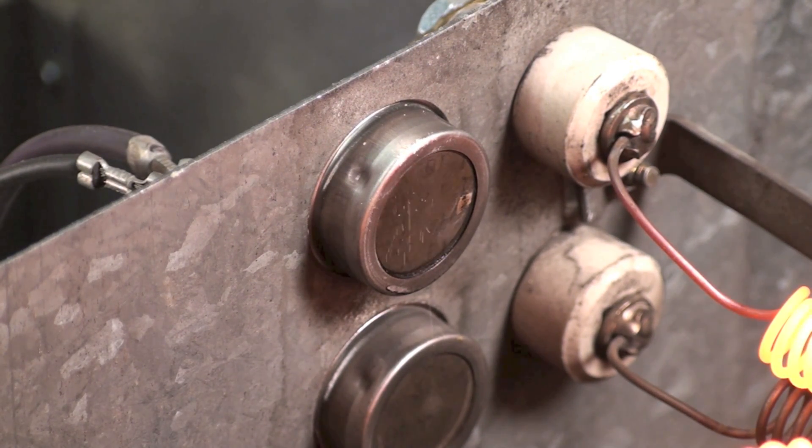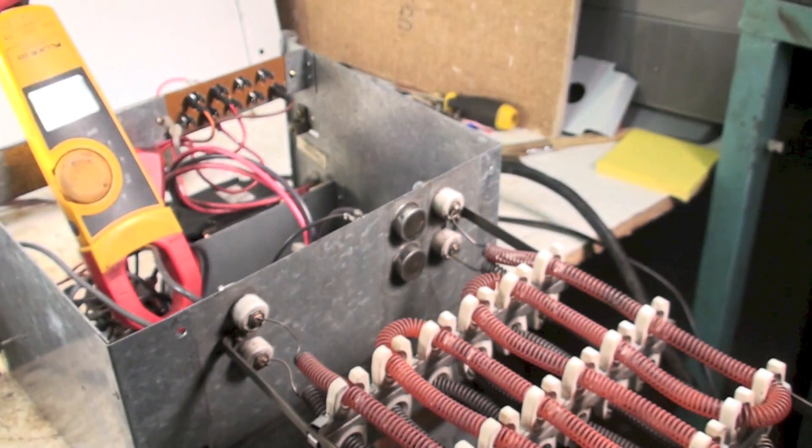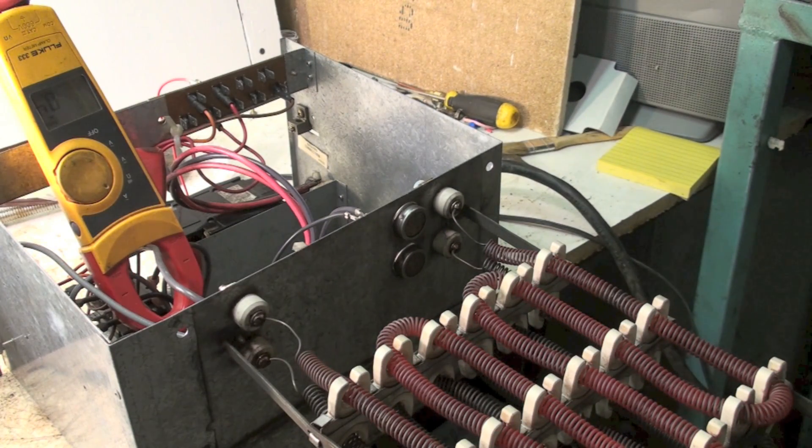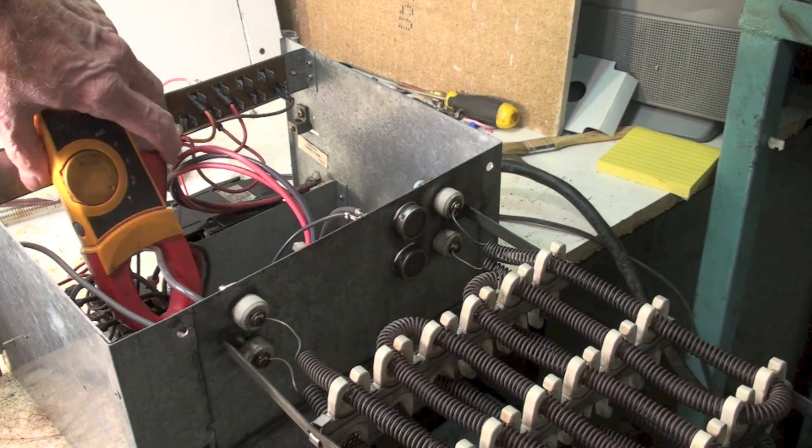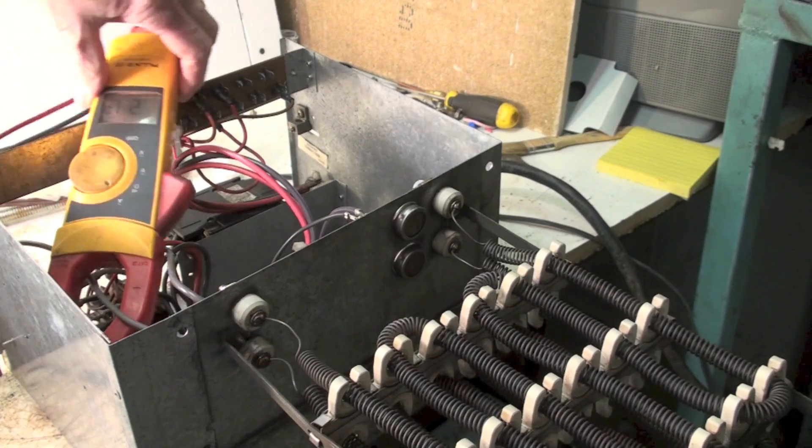And you'll see it pop - there it goes, pop right there. Okay, now you can see the element is cooling down. Now the other one should come on - it's on right now.